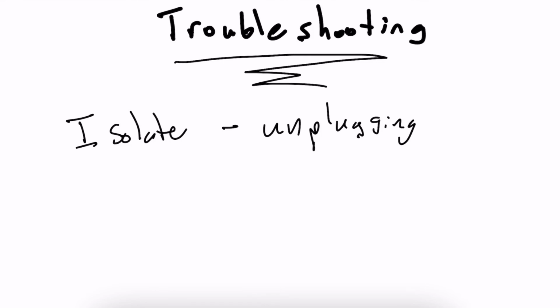Right? Now you want to get that line isolation monitor, that potential leakage current, to get below 5 milliamps. And that's defined due to the effects on the human body as leakage current goes above 5 milliamps. That's why that's defined there. It's the same as or similar to what a GFCI, ground fault circuit interrupter, is set at to go off, to switch off at 5 milliamps. The reason that line isolation systems don't switch off at 5 milliamps, I mean, that would be really bad if you lost power in a surgical room or something of that nature. So they don't switch off automatically, which is good. That's why you use isolated systems, not GFCIs.